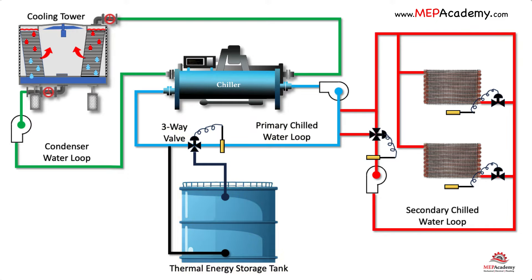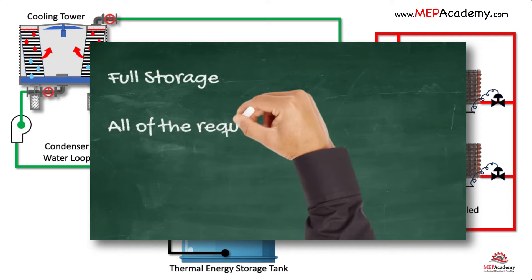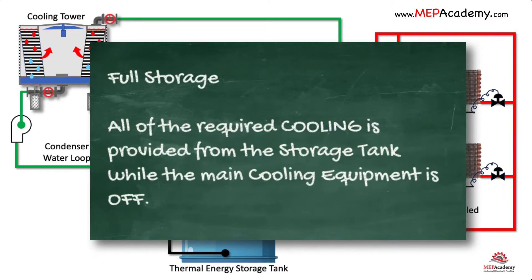The system can run using just the chillers, or the chiller could be run at night to charge the storage tank when electrical rates are cheaper. The three-way valve will close, forcing the chilled water to go through the tank. During the day, when the electrical rates are higher, the chilled water can be pulled from the tank in a full storage system and sent to the air handler coils without the use of the chillers.